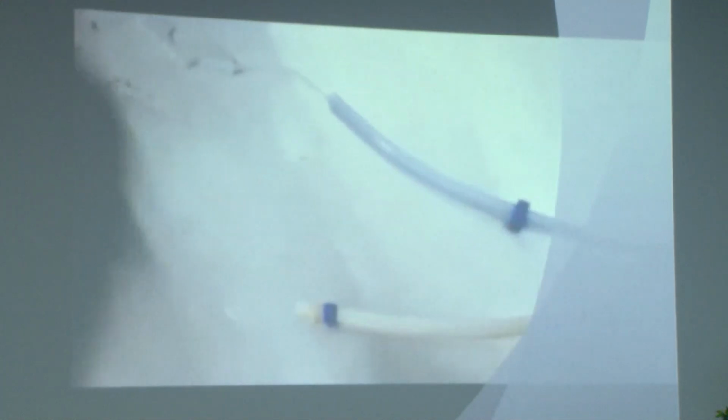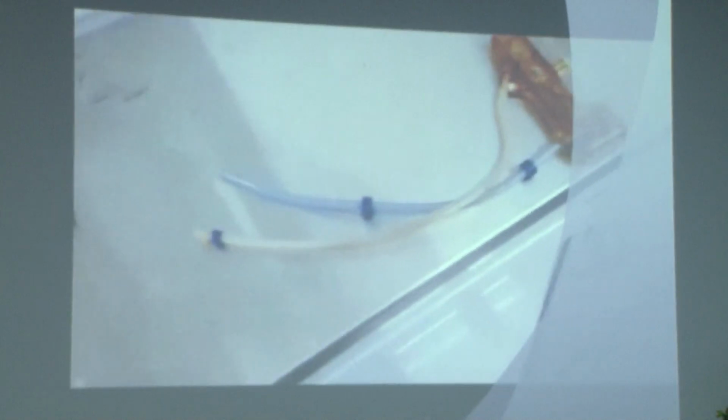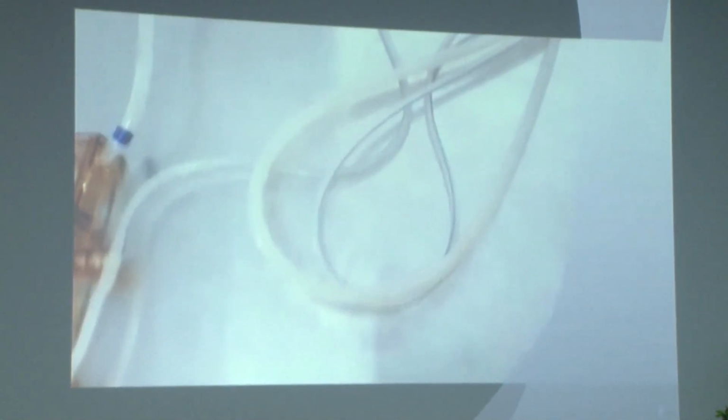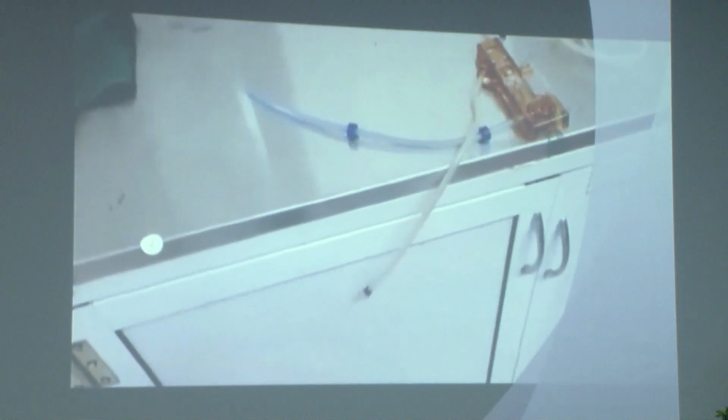So this is very useful if you're reprocessing your instruments immediately, not allowing adequate time for them to get air dried. So here you could see how the moisture is being let out of the phaco tubings immediately using the air gun.